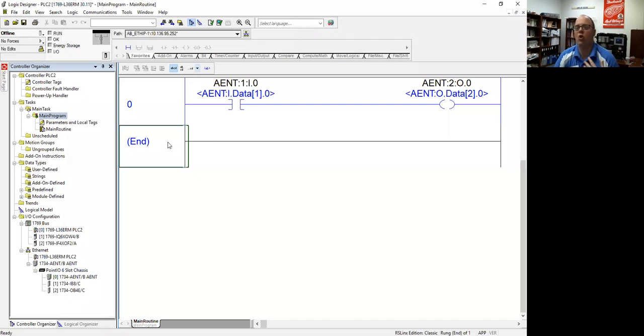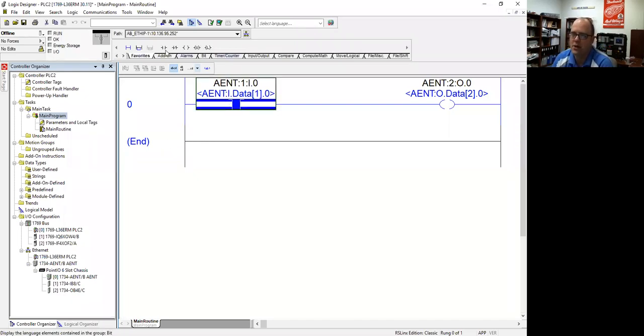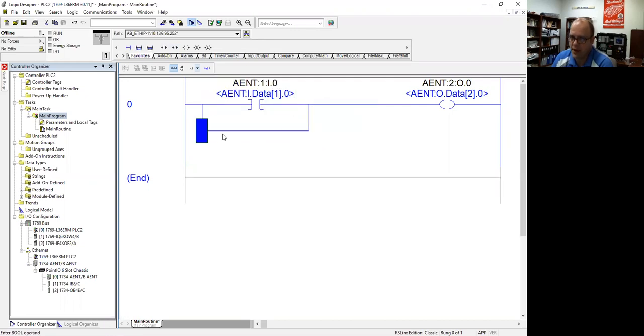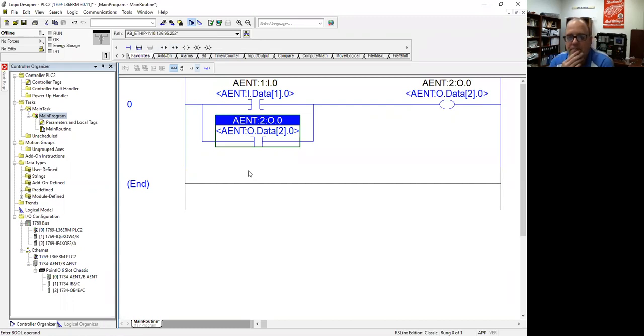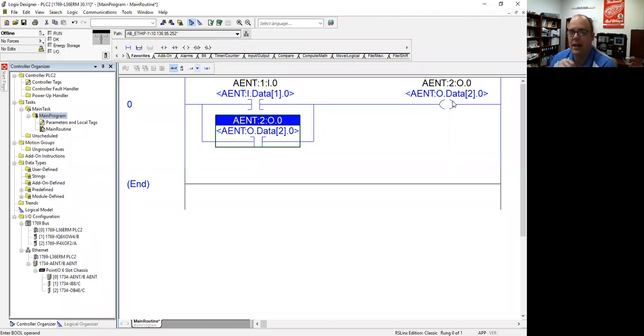The way to think about this is think about the OR logic we've talked about. I'm going to add a branch. If I add another contact and put the output there, stop and consider what we just did: we said if this push button is pressed OR this output bit is true, then turn this on. Logically, when the push button is on, turn on the output, and when the output is on, keep it on — so it stays on at all times.